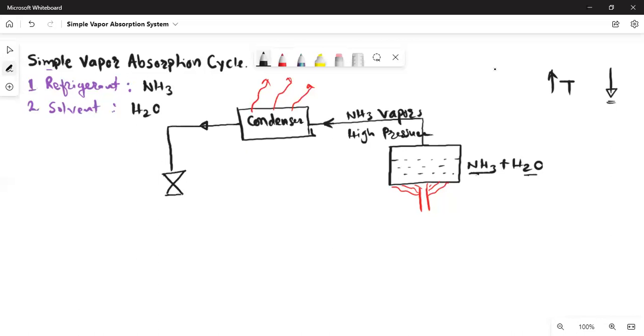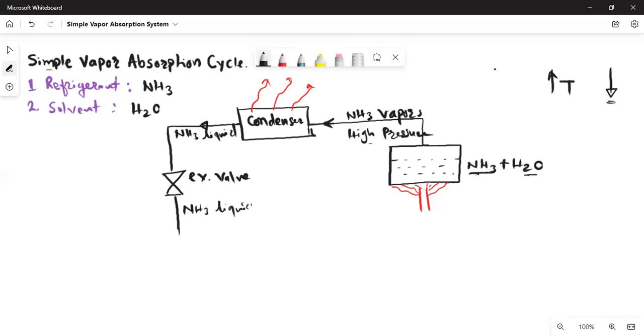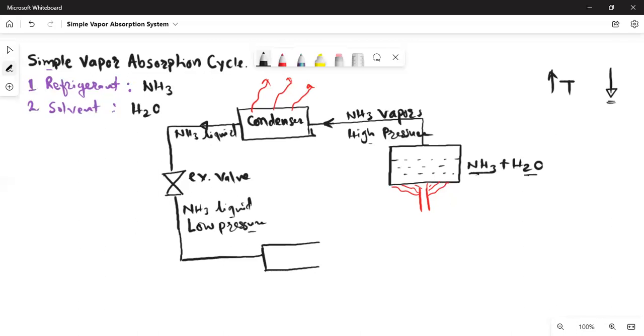The liquid then goes into a pressure-reducing device — the expansion valve. In the expansion valve, pressure reduces. The NH3 remains a liquid; there will be minor flashing but overall it remains a liquid, and the pressure becomes low. It is now low-pressure liquid — a perfect state for use in the evaporator.